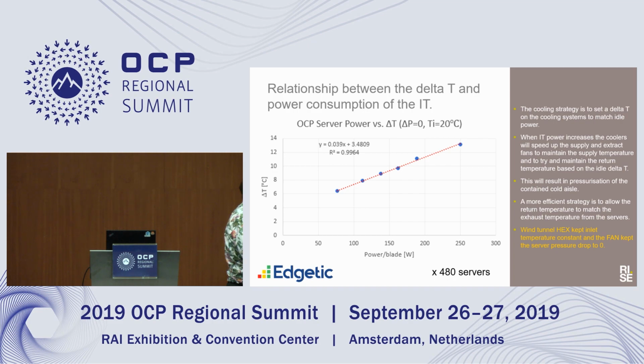For one server, we were able to assess its normal, default operation, where we don't have control of the server fan, and assess the delta T across it. From idle it was at 7 degrees, up to a peak of around 13 degrees at full load.